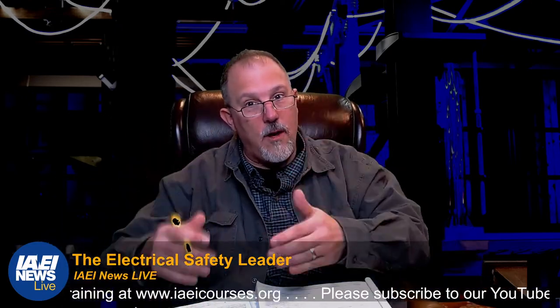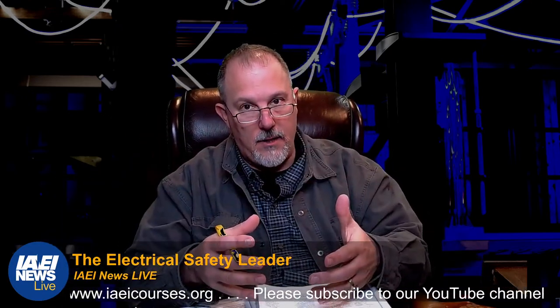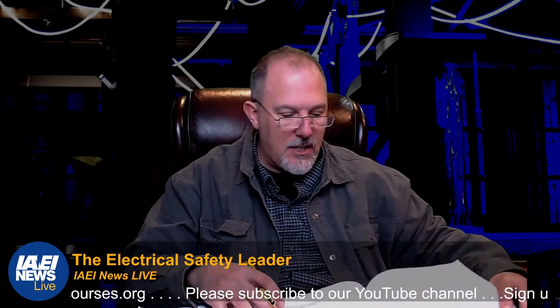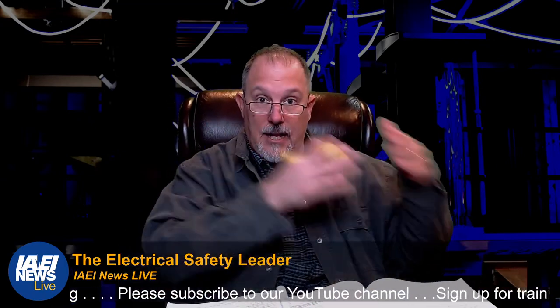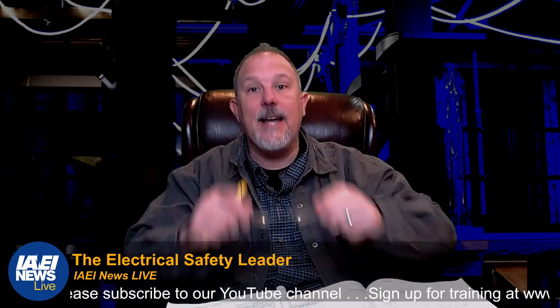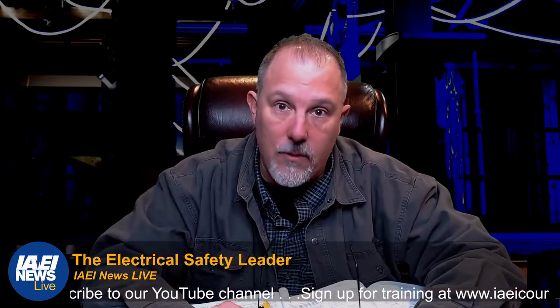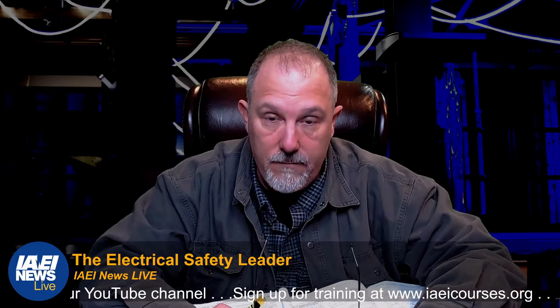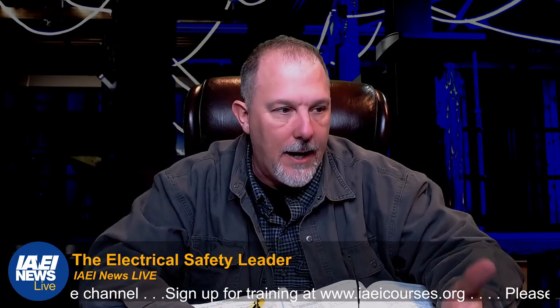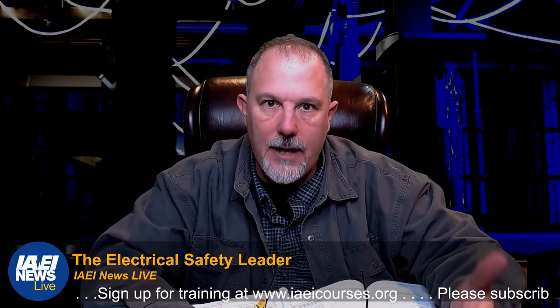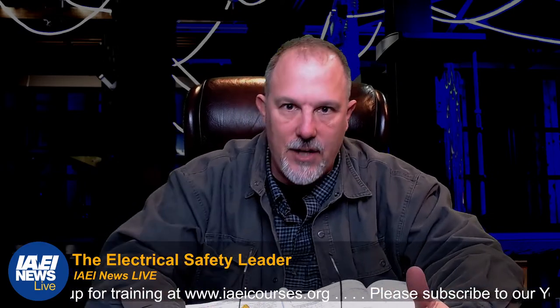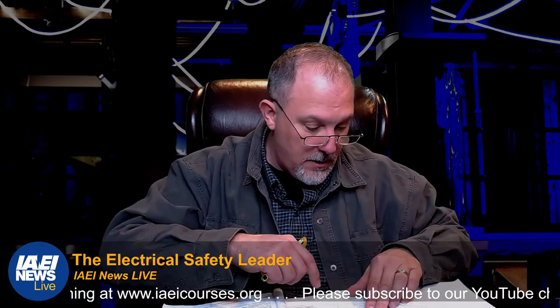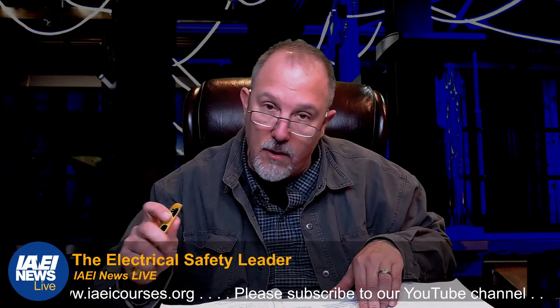So the qualified person requirement here is not that the person has to be qualified to understand the installation. I could say I have never installed an energy storage system in my life, but I know how they work. I know what the safety hazards are. I know there's a shock hazard, I know there's an arc flash hazard. I have met 706.3, the qualified person requirement.